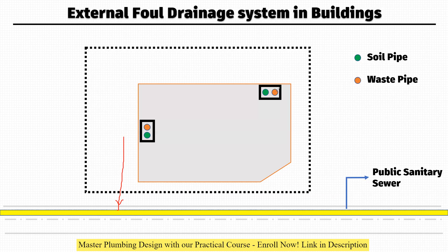For example, this is your soil pipe and this is your waste pipe. The soil pipe will be connecting to a manhole placed somewhere outside the building. As per different standards, this distance should not be more than two meters. The soil pipe — which carries human excreta — goes directly to the manhole. The waste pipe does not go directly; in between we have a gully trap. The wastewater goes to the gully trap first, then from the gully trap it goes to the manhole.